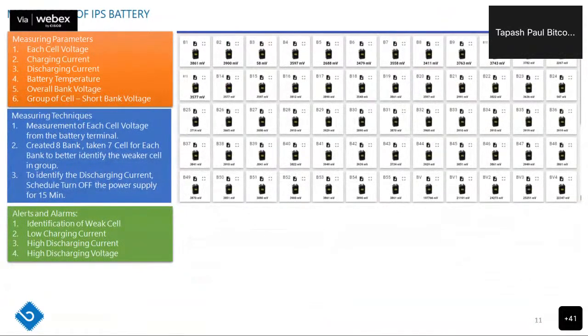In IPS battery, a very important parameter is the discharging state, because the batteries are ideally always in charging state. Whenever any battery is in charging state, we cannot monitor the health of that battery. So we need to monitor it whenever it is discharging, and see how much current and voltage it is taking. Like if I have 55 cells and it is in discharging state, initially it is at minus 20 ampere, and initially when it was in charging state the voltage was 120 volt DC output. And whenever it goes into discharge state, there is a 5 volt drop, so from 120 volt it came to 115 volt.